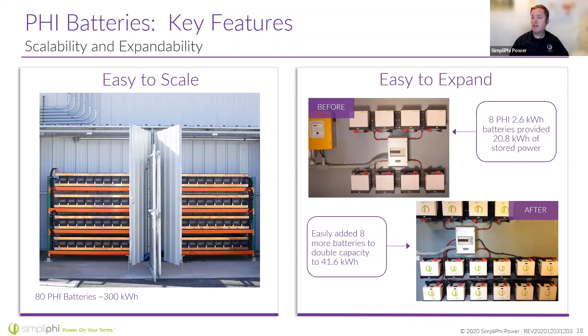One thing I really like about lithium-ion batteries and sealed batteries of any type is that they're self-contained and stable. They're not going to vent or release gases. You don't need to do any work over time. So when you sell a system, you don't need to set up scheduled maintenance with the homeowner, or the homeowner might say, don't worry, I'll water my batteries. Inevitably they call you a couple years down the road because they didn't water their batteries, and the whole battery bank is fried. By not needing to worry about maintenance, you can spend your time doing new installs instead of coming back to maintain these batteries. You're not going to have that vent fan because you're not releasing any gases.